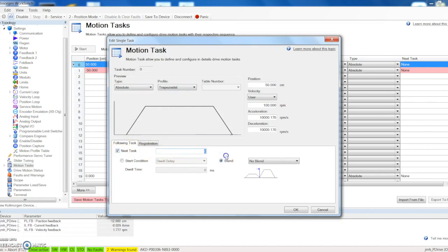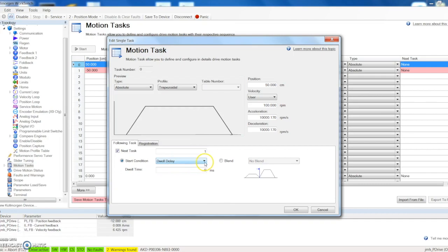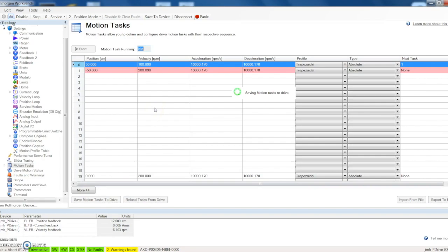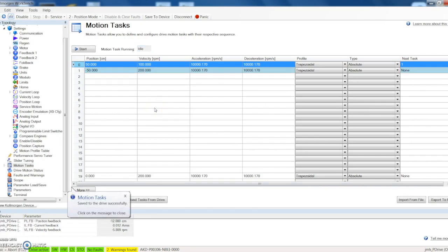Another nice feature: let's say that we know that we're going to have constant motion and we know what that motion profile is going to be. We're always going to stroke out to 50 centimeters and let's say we were always going to come back home, so we're going to go negative 50 centimeters because we're doing an absolute position move. So we're saying I need the servo motor to go in reverse 50 centimeters. So we want that at 200 RPM. Let's save that. Now what we can do here in position 0 is we can do a following task. If we select next task and then now select our new position 1, we can select position 1, we'll start a condition, and we'll delay the move by 500 milliseconds. Let's select OK. We're going to save that task, and now that is saved we can call that motion.